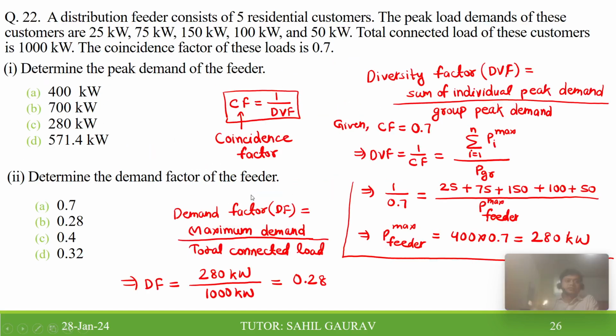So in this problem, problem number 22, it is asked that a distribution feeder has five residential customers, and the peak load demands of these customers are given as 25 kilowatt, 75 kilowatt, 150 kilowatt, 100 kilowatt and 50 kilowatt. The total connected load of these customers is 1000 kilowatt. The coincidence factor of this load is 0.7, and there are three questions based on this statement. The first part is to determine the peak demand of the feeder.